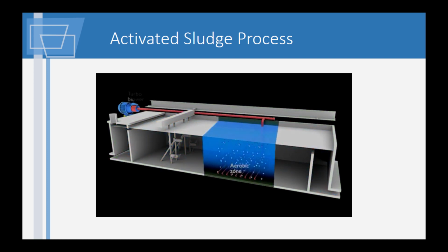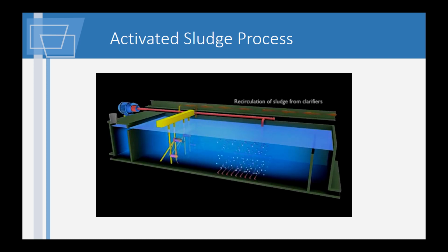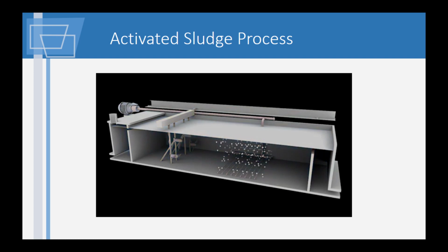During the aeration phase, specific bacteria eat the dissolved organic matter and transform it into suspended solids. Other specific bacteria oxidize the ammonia into nitrites, then nitrates. During the non-aeration phase, also called the anoxic phase, another type of bacteria convert the nitrates into nitrogen gas, which is released into the atmosphere. To ensure a good balance between food and bacteria, the bacteria settled in the clarifiers are continuously returned at the inlet of the tank. They are called return activated sludge. The upstream part of the activated sludge tank is covered so that odorous air is trapped and extracted towards odor treatment units.